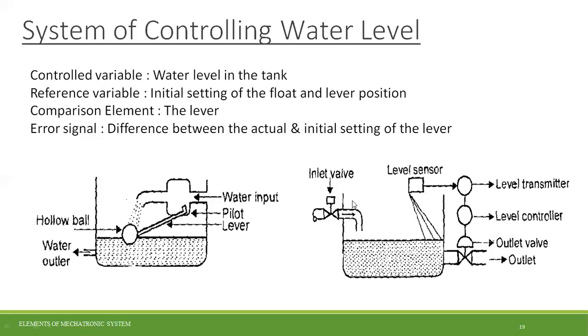Simultaneously, when the water level in the overhead tank reaches a minimum range, the level sensor automatically senses the signal and transmits it to the level controller, which initiates the electrical power supply, and the motor automatically switches on to fill the water tank. After reaching the maximum point, the same level sensor sends signals through the transmitter to the controller, which then signals the electrical motor to switch off automatically. This is what we call an automatic system.